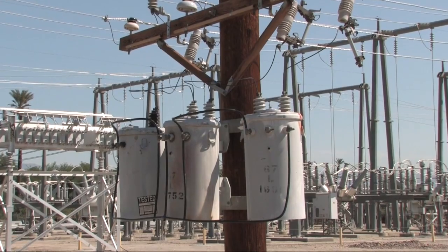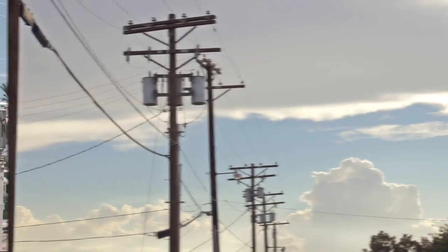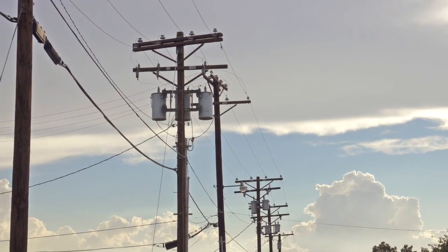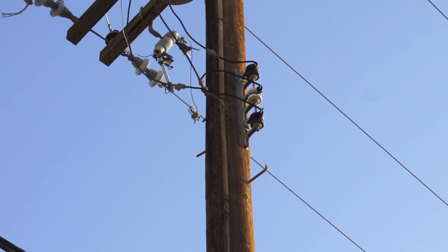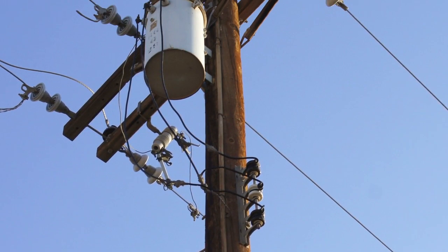At overhead transformer banks, which are typically metal canisters at the top of a power pole, the voltage is stepped down to a usable voltage for a home or business, which is in the 120 to 480 volt range.